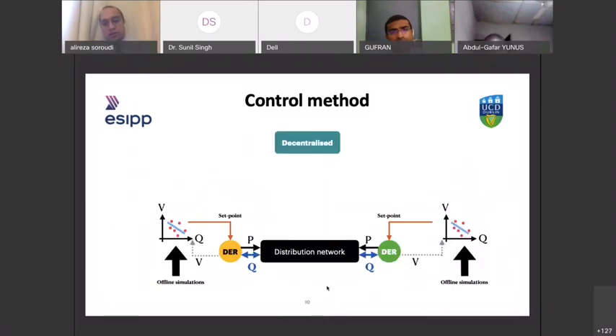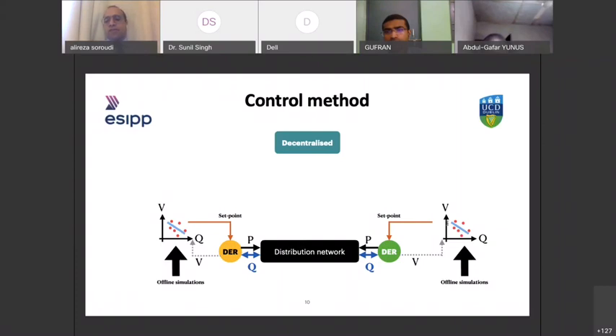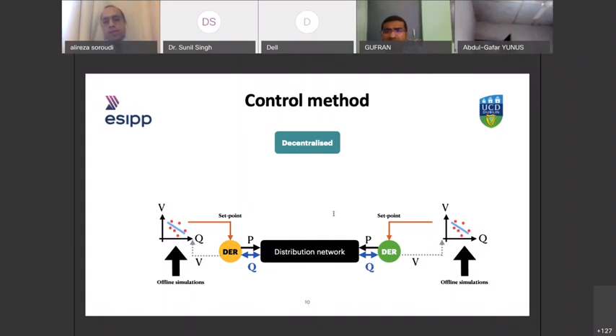In the decentralized approach, we do the same offline simulation and tuning, but devices act based on their own understanding of what's happening in the grid. They sense the voltage at the connection point, feed it to their VVC curve, and that VVC curve — which is tuned for each DER individually — gives the set point, changing the reactive power accordingly.